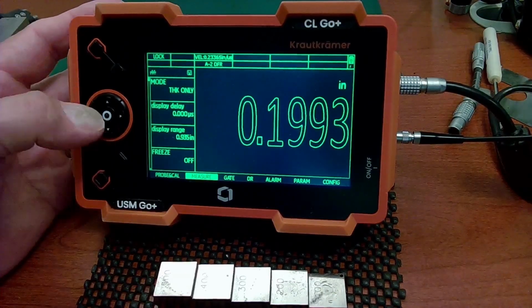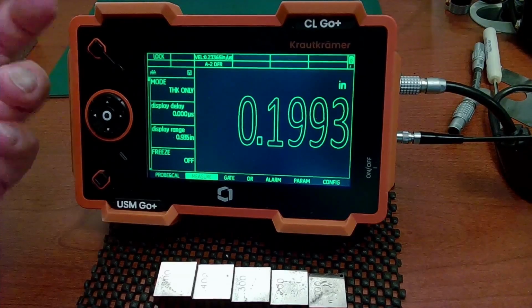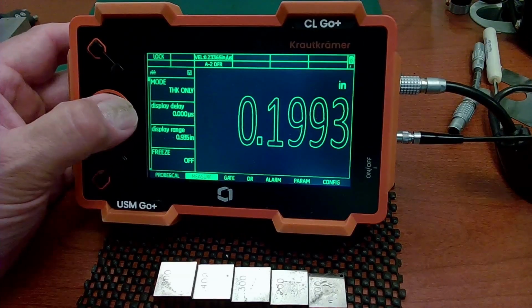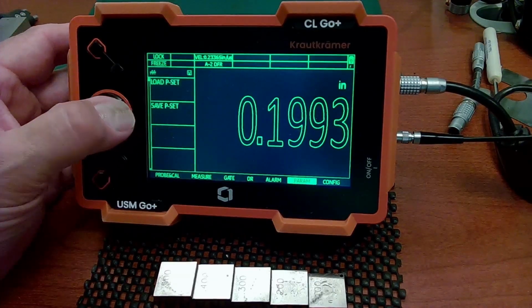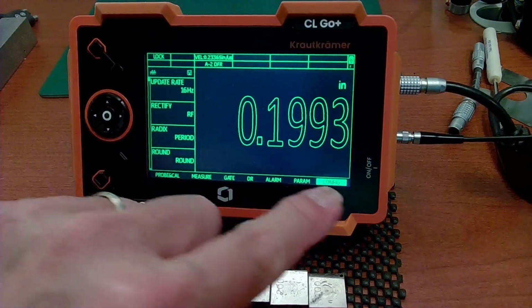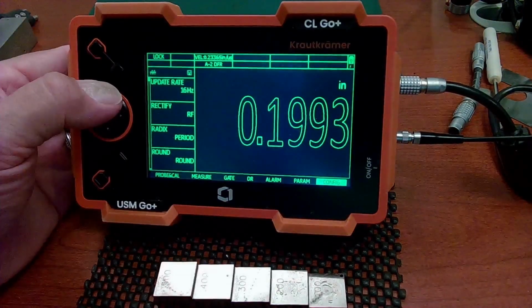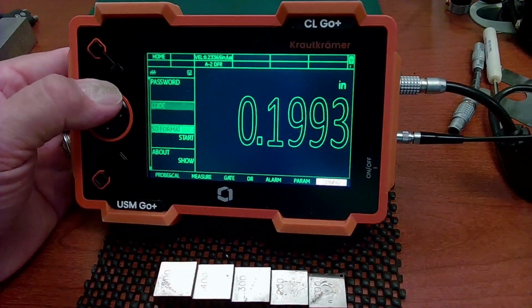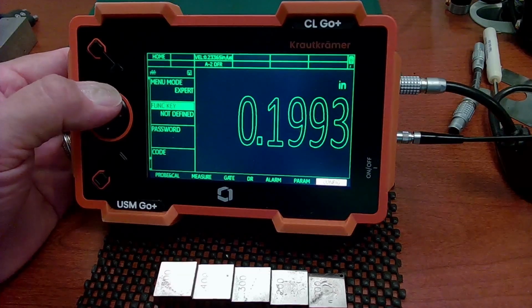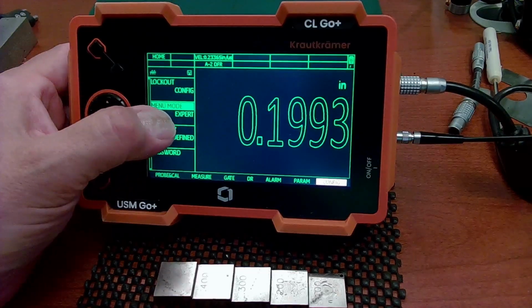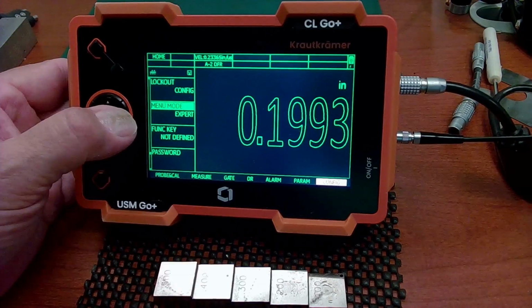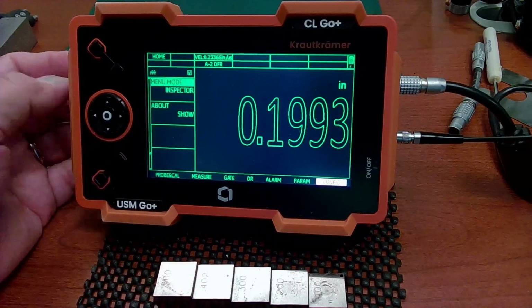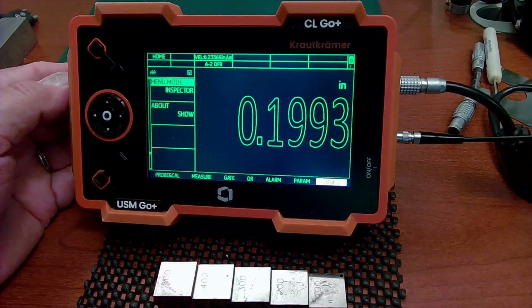There is a simpler mode that depends on that initial setup being correct for most materials most of the time. If we come over to the config menu and up to menu mode, notice right now that's selected as expert. If I select inspector, that provides a much simpler set of menus.